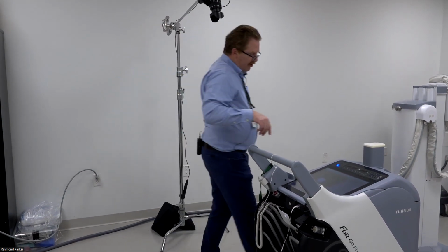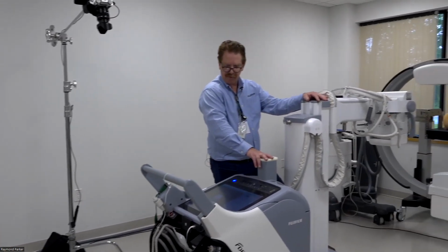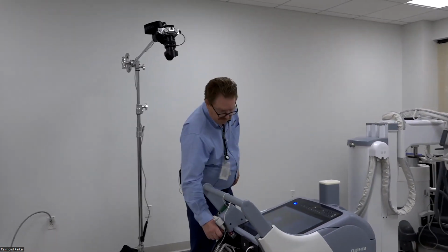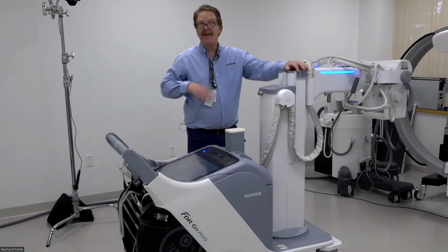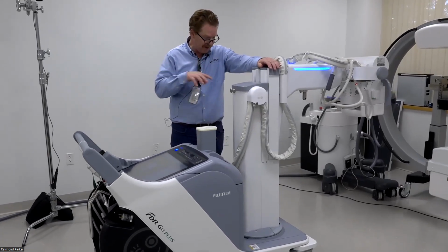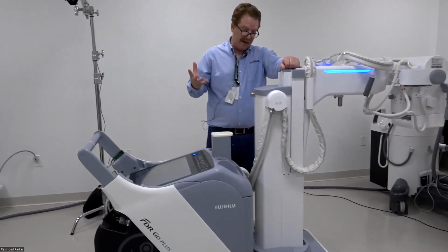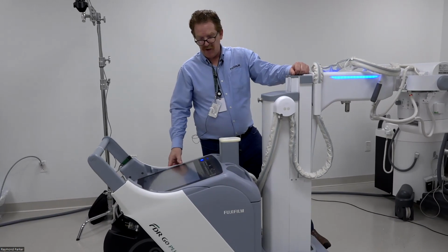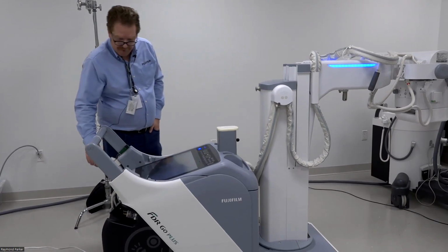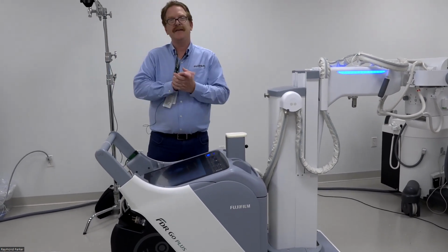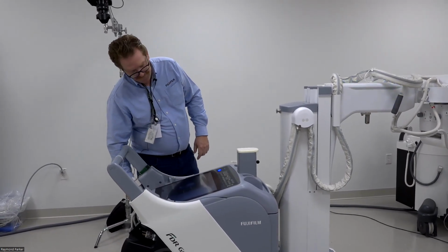The other one I wanted to show today is the bumper detection override. The bumper detection override happens to all techs. We run them into a wall. You hit a wall so hard that you've either bent the carriage for the sensor or damaged the sensor. In that instance, you have this lovely beeping sound.